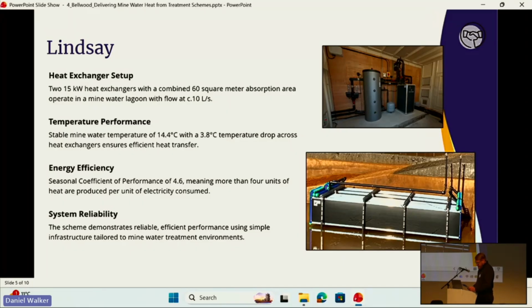At Lindsay, the mine water is 14 degrees, and across the heat exchangers we see a drop of around 3.8 degrees. That energy feeds a 35 kilowatt heat pump into the thermal earth building. In the first year, the seasonal coefficient of performance was 4.6, so for every unit of electricity used, the system delivers more than 4 units of heat, demonstrating how effective mine water can be as a heat source.